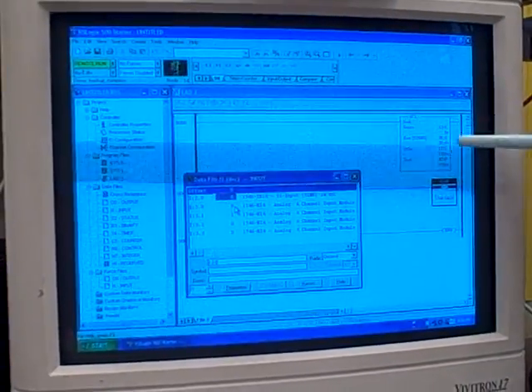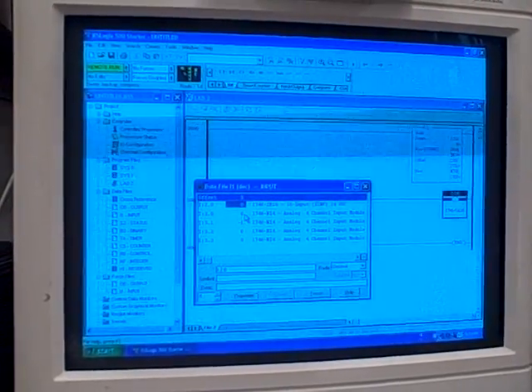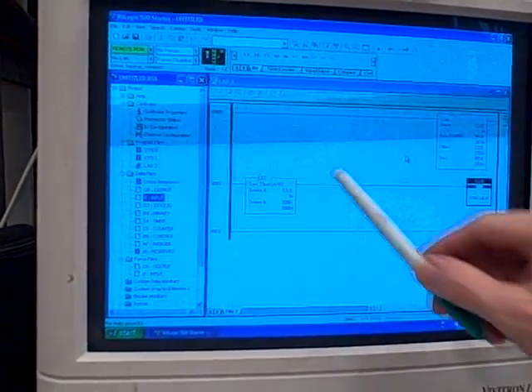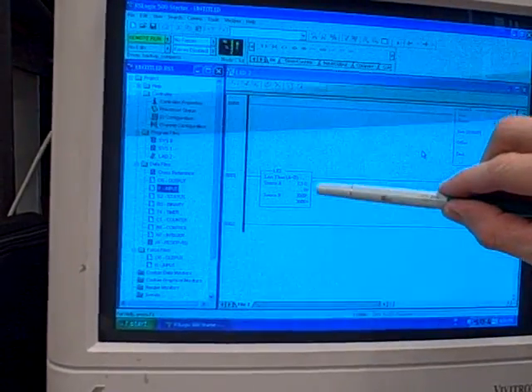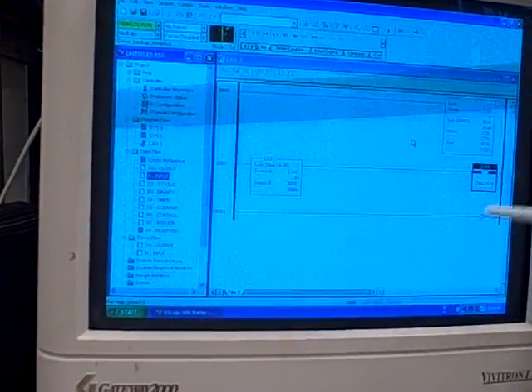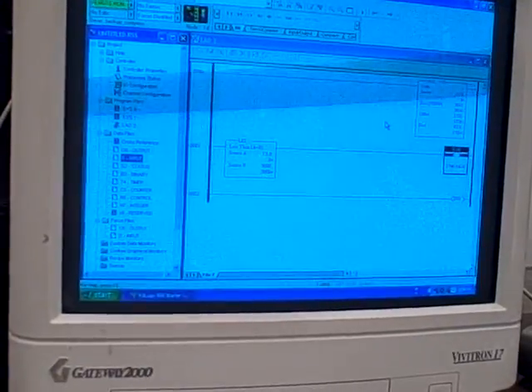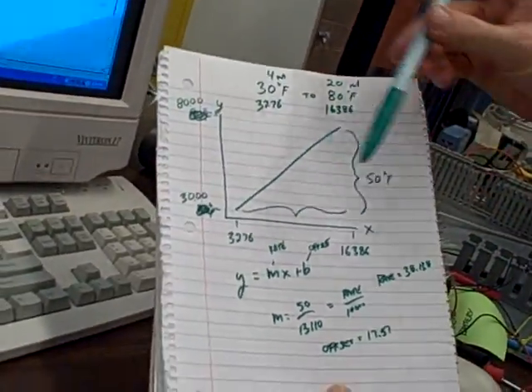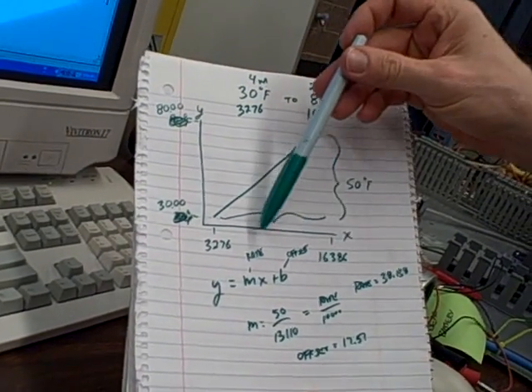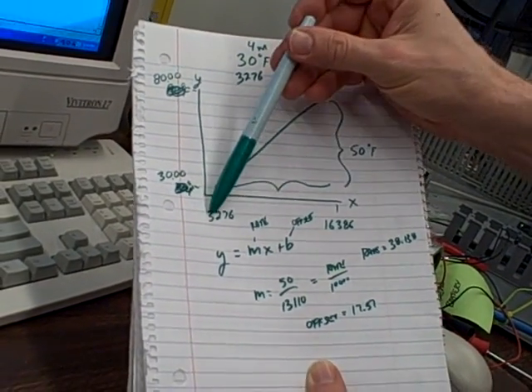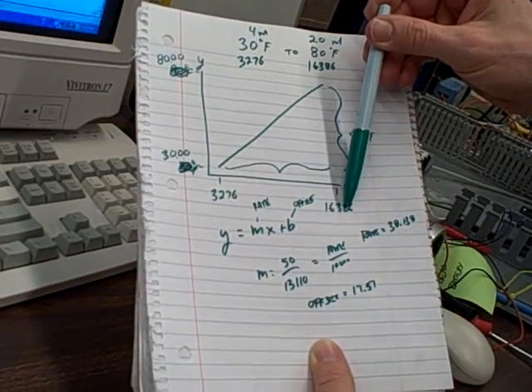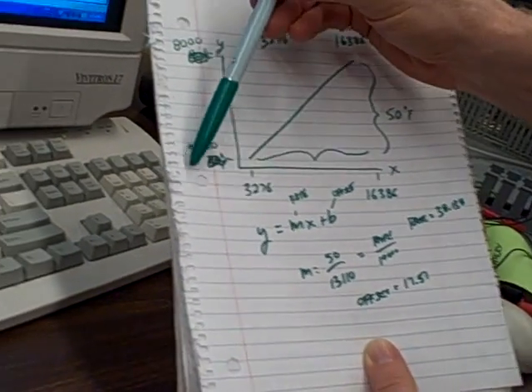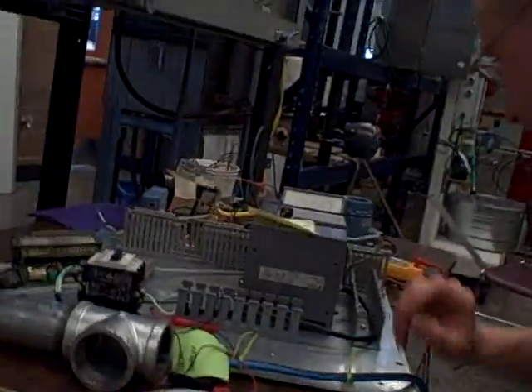We've already talked about doing the scale command here. We've added one more rung to the program that's going to examine that analog input value. If it falls below a count of 3,000, it's going to flag an output saying we've got ourselves a bad loop. Because we found out through testing that 4 to 20 milliamps in the analog input channel gives us an A to D converter count of 3,276 to 16,386. So we figure anything below 3,000 is significantly below 4 milliamps. We've got some sort of problem with the wiring or with the instrument.